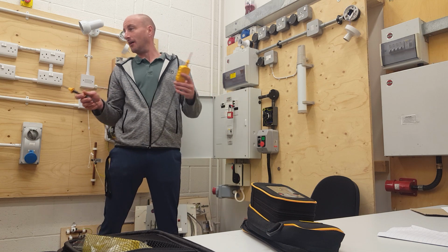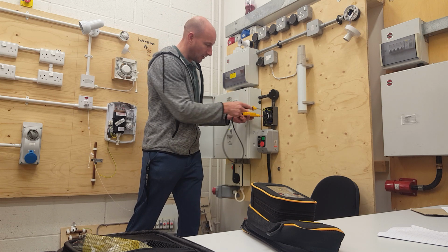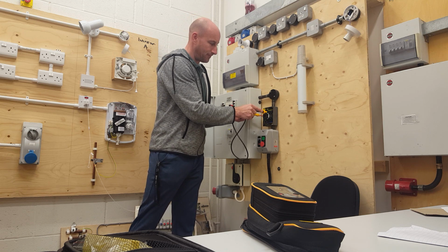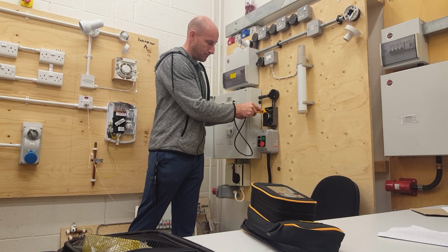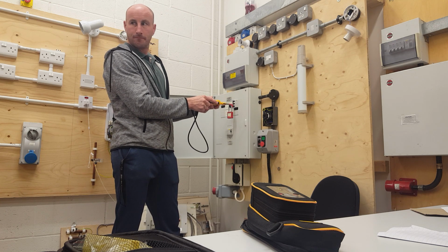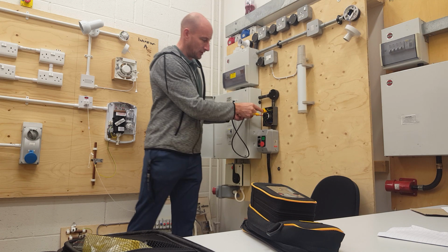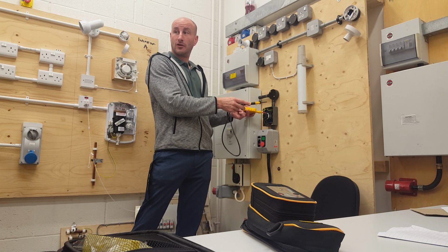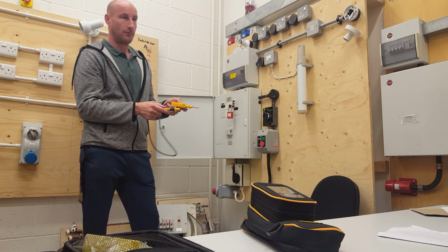So what are the 10 tests then? Earth to line, all of them: earth to live 1, live 2, live 3, and then earth to neutral. Then L1 to L2, L1 to L3, and L2 to L3. Or your lives to neutral. We did that. Earth to neutral. I think that's it, I wasn't counting. But we did all the lives together, and then all the lives to neutral as well. We did all the earths to neutral, 1, 2, 3. So the neutrals to live as well.